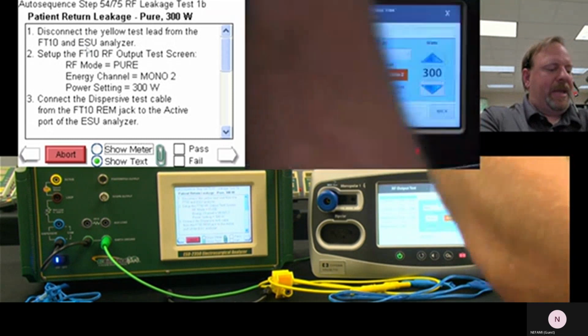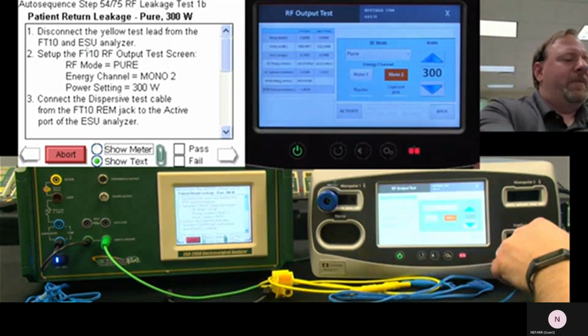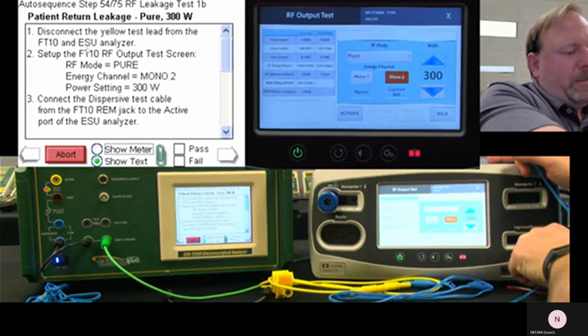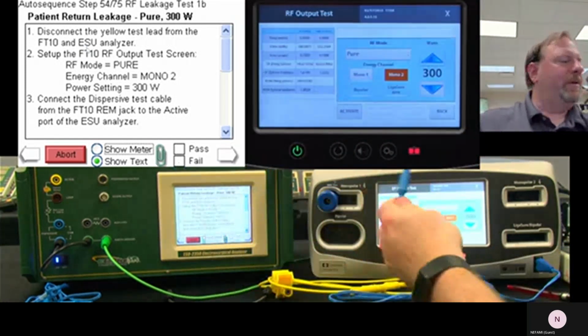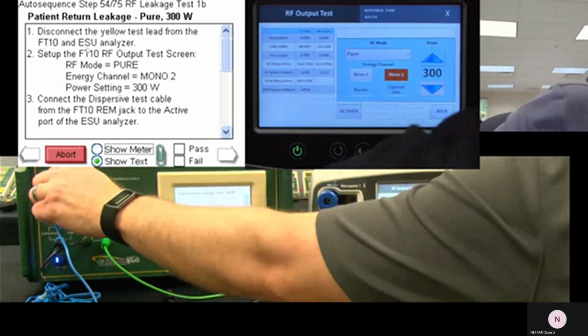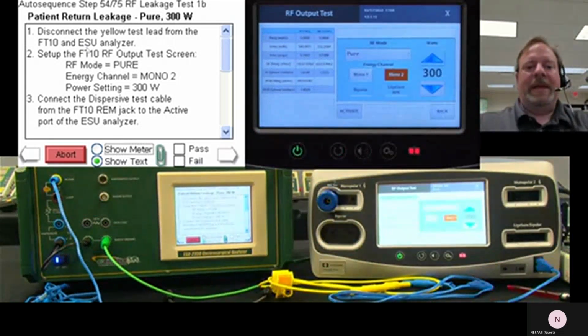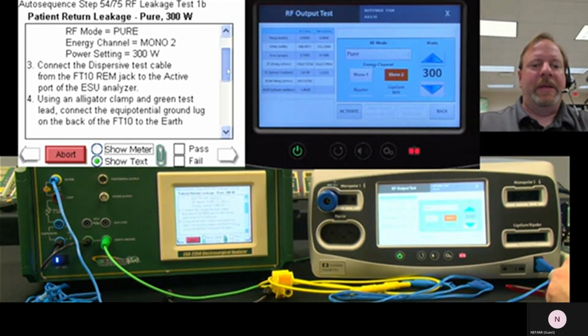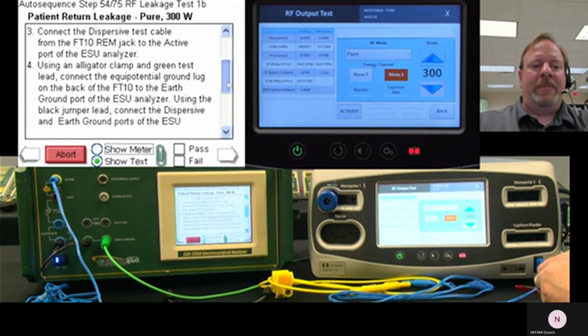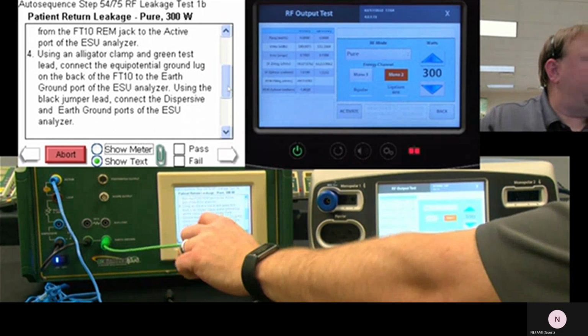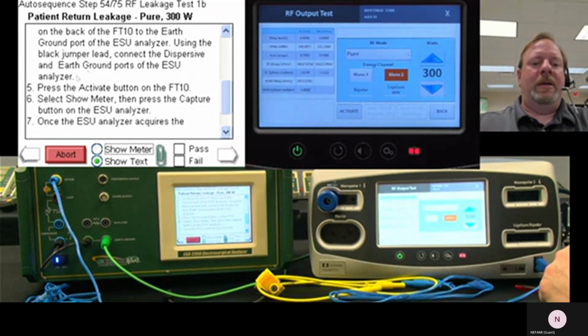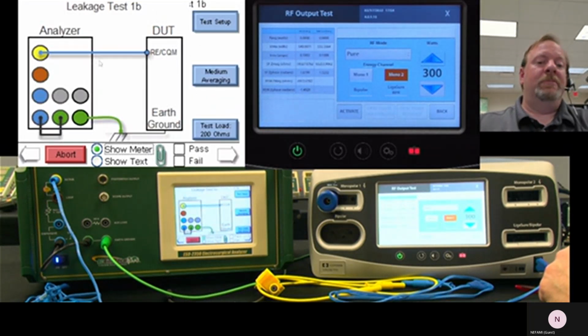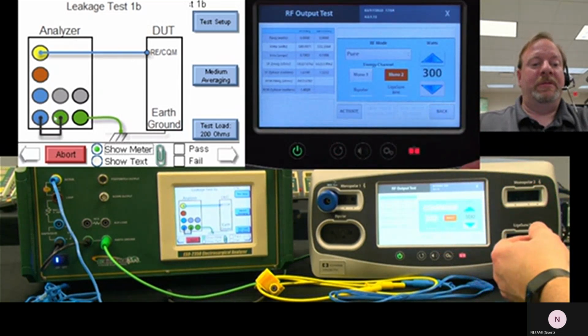Well, this is why this cable is in the accessory kit, because if we're measuring the current from the return electrode, we need a single connection to go to active. The whole purpose of that cable. Now we got to make use of it. Dispersive cable, FT10, using alligator clamp. We already got that. Still there, green to the back. Connect the black jumper lead, dispersive, earth ground. Got it. Again, if I have any question, if maybe I like pictures better than words, great.